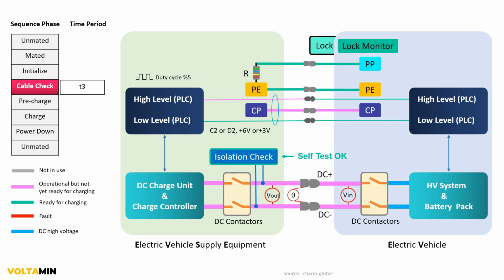The communication lines, including CP and PP, are operational and actively verifying system conditions. The isolation check ensures there are no insulation faults in the system, verifying safe conditions. The lock monitor confirms the plug is securely latched, and the proximity pilot, PP, verifies the connection and cable's capacity. This phase ensures all safety and connection parameters are validated before moving to the pre-charge phase.